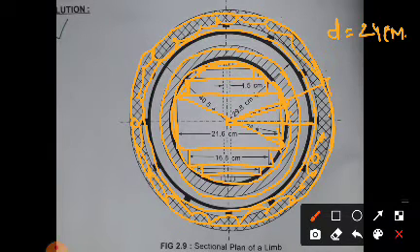So this is the LT winding, and the thickness of the core is also the same. This is a limb, whether it's R phase, Y phase or B phase, where the core material is surrounded by the LT winding and HT winding. In between there is an air gap to flow the oil or some cooling media. So this is one winding. Similarly for the R phase, given the distance between center core to center core, you draw another similar core and winding limb side by side, three limbs. You get the three phase.